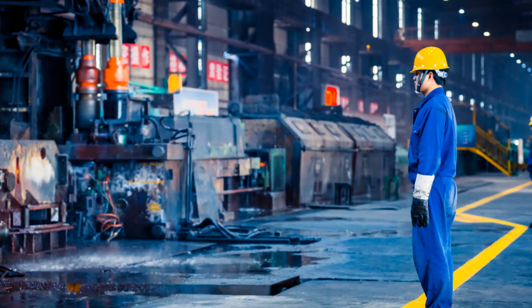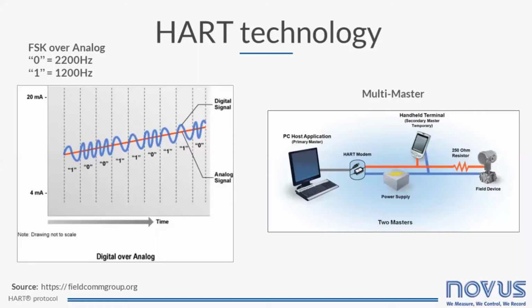Now, let's talk a little bit more about the HART technical features. HART uses FSK, frequency shift keying, a modulation technique called the Bell 202 standard, to superimpose a digital signal on top of the 4-20 milliamps. Using this technology gives the operator easy identification of the field device by its tag and allows verification of all operational parameters.